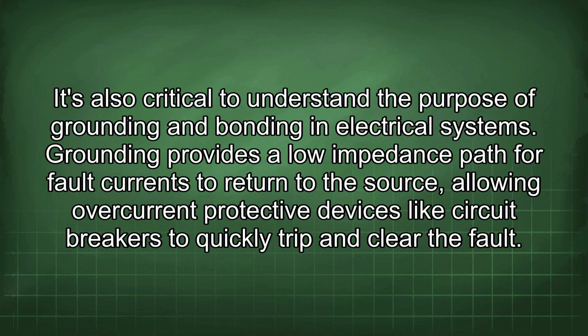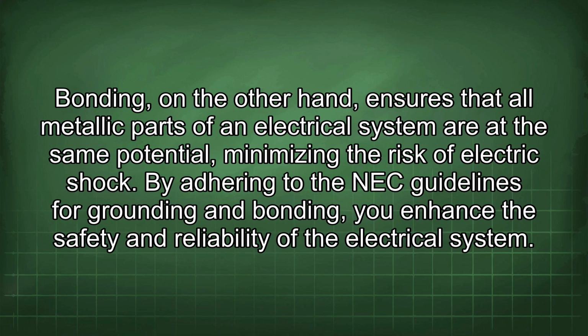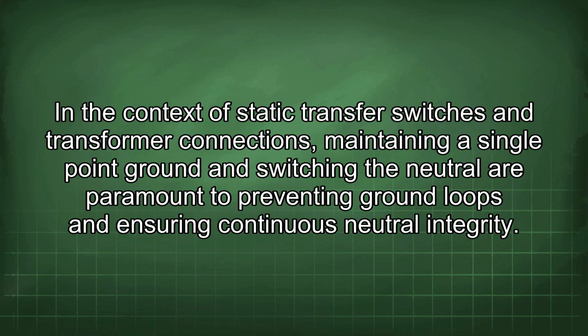It's also critical to understand the purpose of grounding and bonding in electrical systems. Grounding provides a low impedance path for fault currents to return to the source, allowing overcurrent protective devices like circuit breakers to quickly trip and clear the fault. Bonding, on the other hand, ensures that all metallic parts of an electrical system are at the same potential, minimizing the risk of electric shock. By adhering to the NEC guidelines for grounding and bonding, you enhance the safety and reliability of the electrical system. In the context of static transfer switches and transformer connections, maintaining a single-point ground and switching the neutral are paramount to preventing ground loops and ensuring continuous neutral integrity.